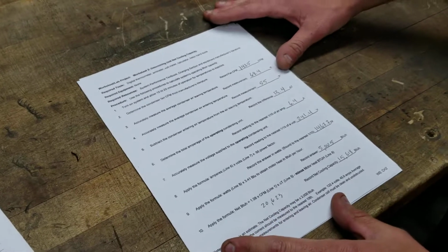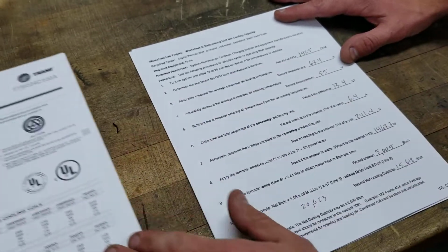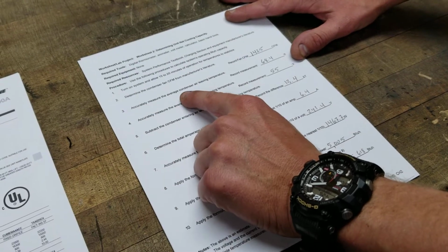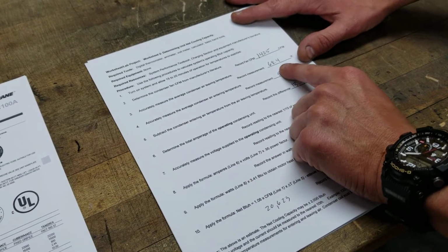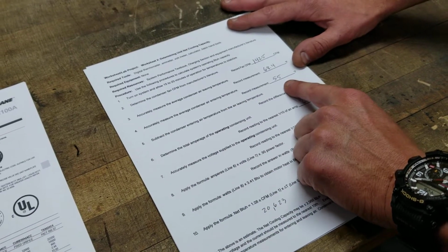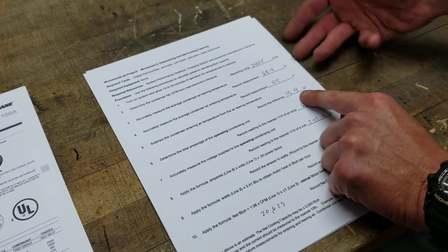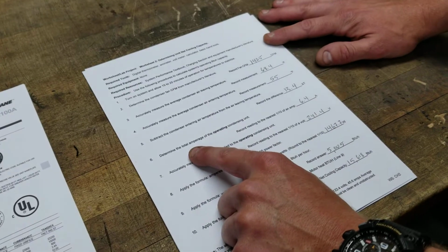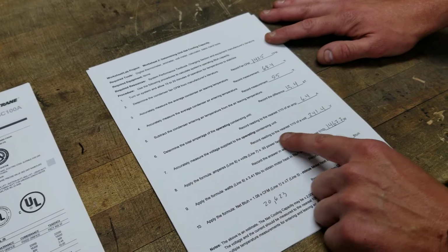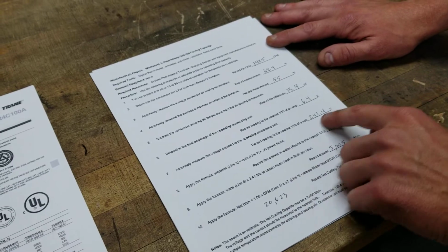So here's our worksheet example. First thing we need to know is our fan CFM. It's 1425. We got it from the manufacturer. The second thing we need to know is the average condenser air leaving. I averaged it at 68.4. We need to measure the air entering. I measured at 55. That delta T, the difference between the two, is 13.4. Our total amperage, when I did this test, was 6.4 amps. Our voltage, I measured 241.4. We're going to round this to the tenth.